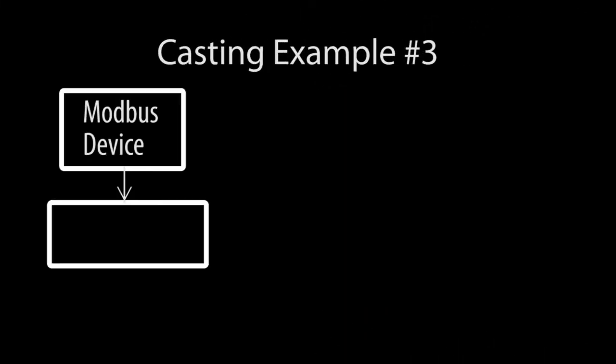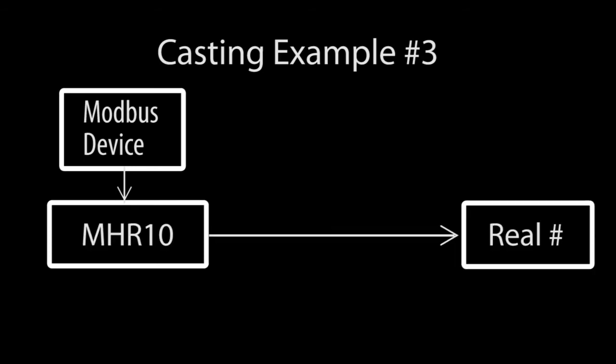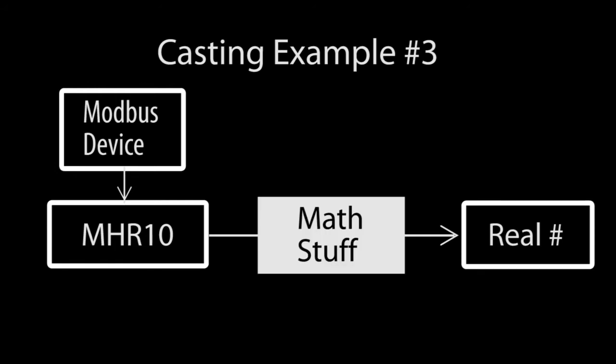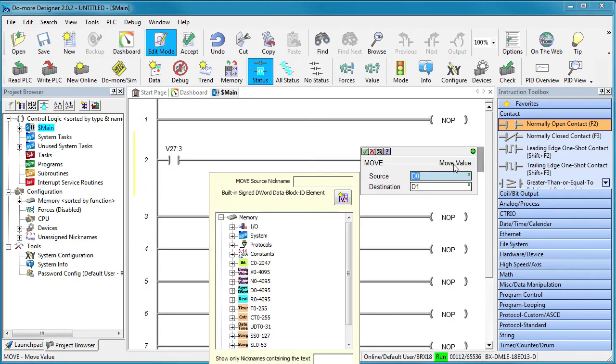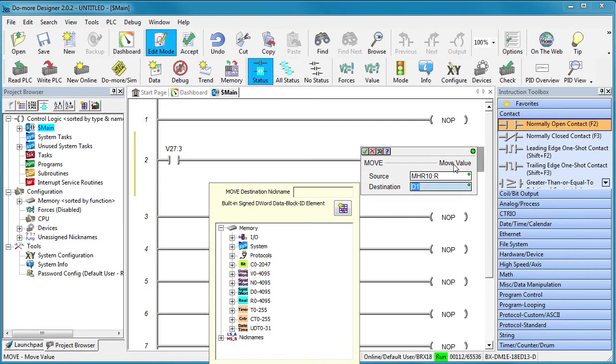Suppose you receive a number from some other device in Modbus Holding Register 10 and you know it is intended to represent a real number. Again, you could do a bunch of math to convert it into a real number format or you can use casting to simply tell Do-more to do it for you.